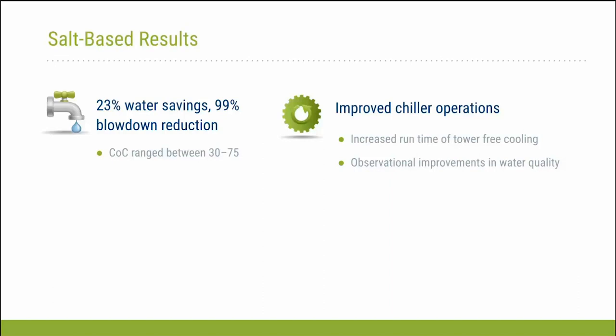I would say for this building and the next one that I'm going to talk about, there was some existing scaling in the systems that was eliminated through the use of these products. I think to that question on energy savings, our experience is essentially, if there is any existing scaling in the plate and frame heat exchangers for water side free cooling or in the condenser tubes in the chillers, you probably have a decent opportunity for energy savings. If those are pretty clean as they are, then obviously there's not an opportunity for energy savings. Again, on this one, since we did not have the M&V equipment installed beforehand, we didn't measure the energy savings here, but the site did report an increased runtime of tower free cooling and energy savings with this one as well. Okay, next slide.